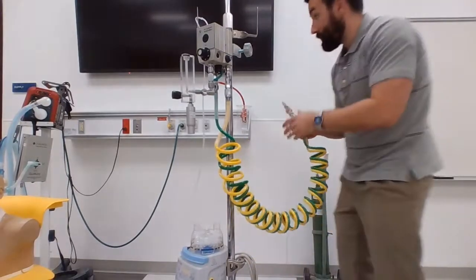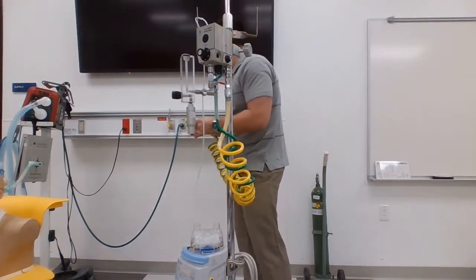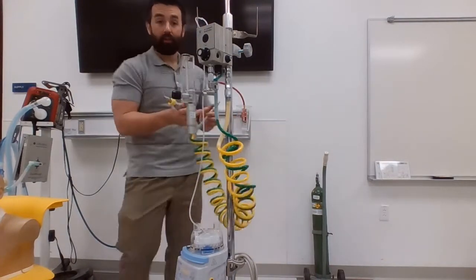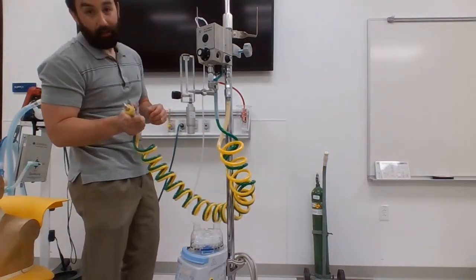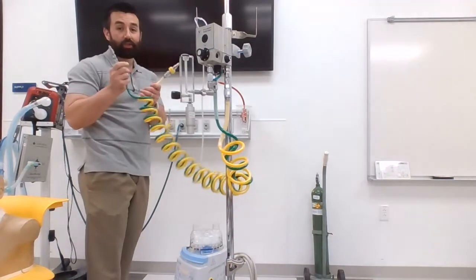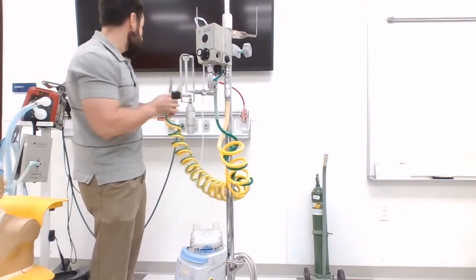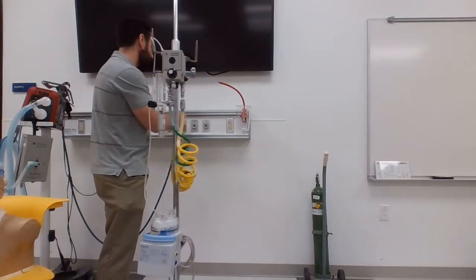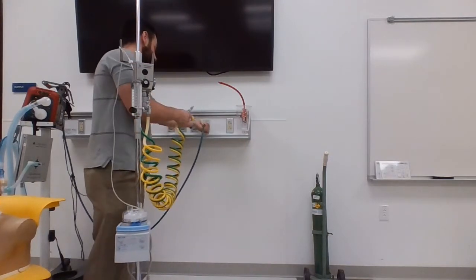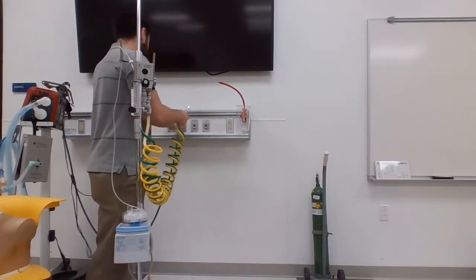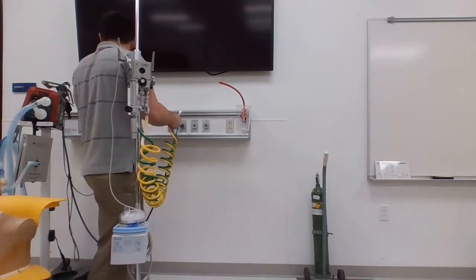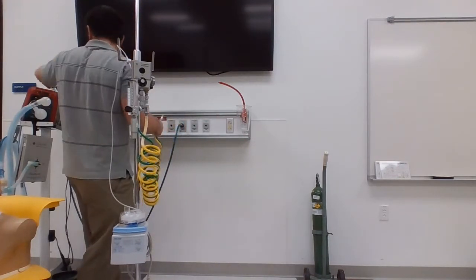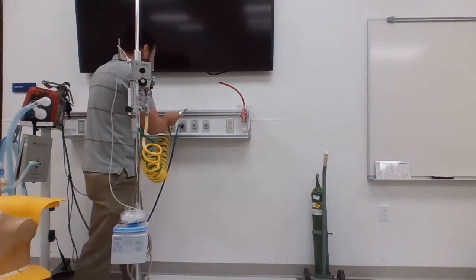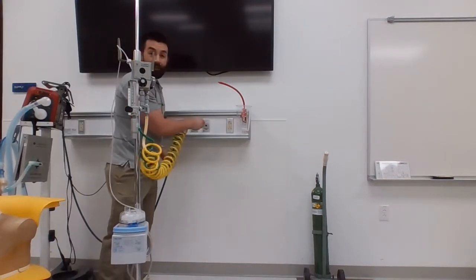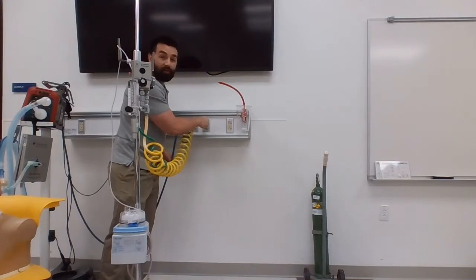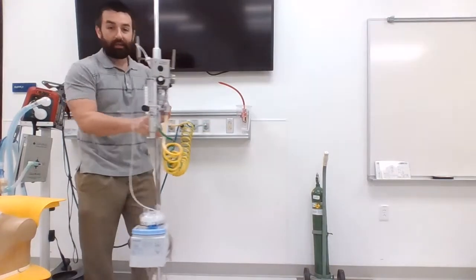I'm going to introduce you to a common alarm that takes place, and that's a blender alarm. So if something happens and I lose one of my 50 psi sources, as I'm going to show you here, it's going to make a very distinct alarm noise. You're going to also hear a ventilator alarm here in a second. Hang on. Let's try to avoid the ventilator from alarming. So I'm going to plug in my air connection, and you can hear that loud whistle. It means I don't have one of my 50 psi sources.